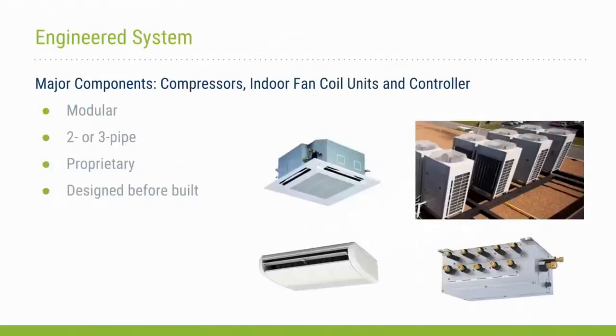One important aspect of VRF systems is that they are fully engineered systems. All of the equipment, including an integrated control system, is provided by the manufacturer. These systems are modular and have a limited number of components. They include, as you can see in the picture, some indoor fan coils, outdoor units, and a controller box. Each of these components are relatively small, so installation is relatively easy. In fact, an outdoor unit can be transported to a roof in a 6-person elevator.